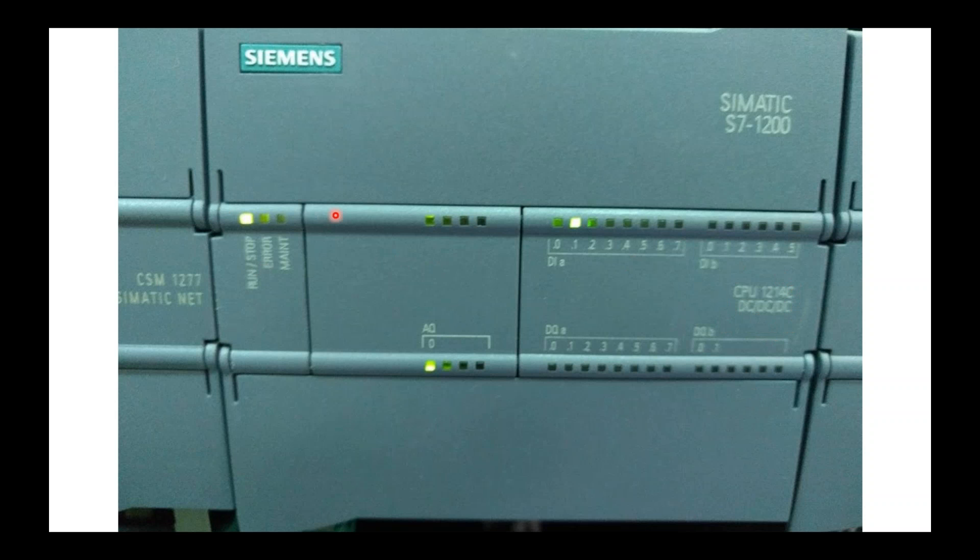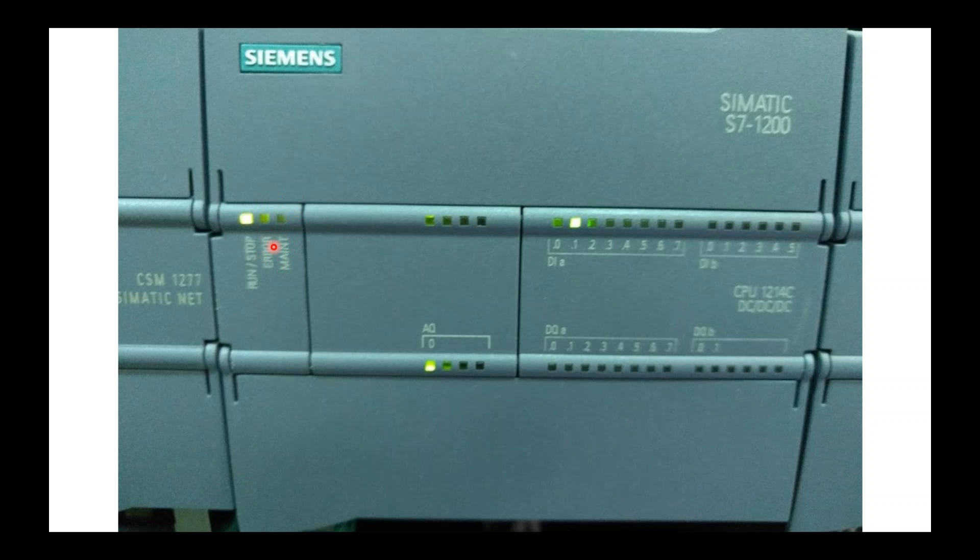Also right here is your status lights. If it's green, it's in run mode. If it's like a red, it's in stop mode. If you're doing some type of forcing or doing some type of diagnostic, this maintenance light will be on. And of course, error is self-explanatory. If you've done something to blow the processor up or it doesn't understand something or there's a power issue, this will be in error.